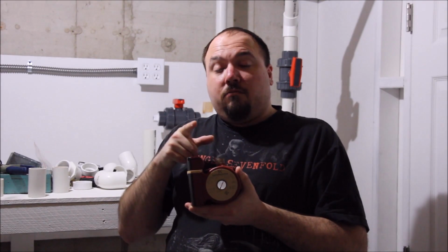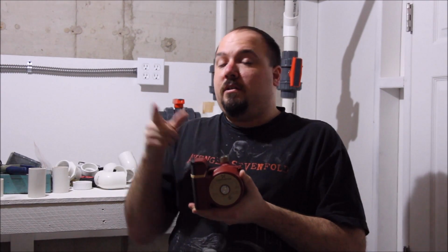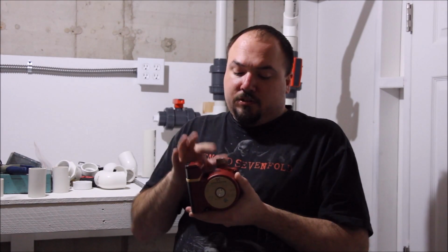In reading the forum posts about it, and I've put a link to that in the description below, someone had challenged the original design that VLDesign.com used, stating you can't use a cast iron pump in this type of situation because it will start to corrode and rust, since it's not a closed system, and that's all cast iron pumps are designed for.